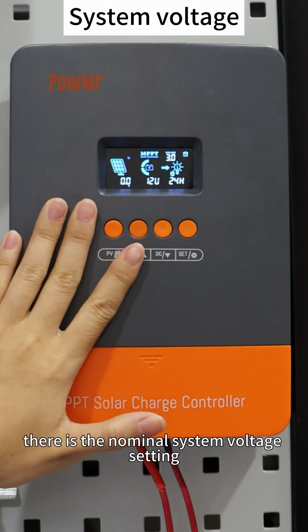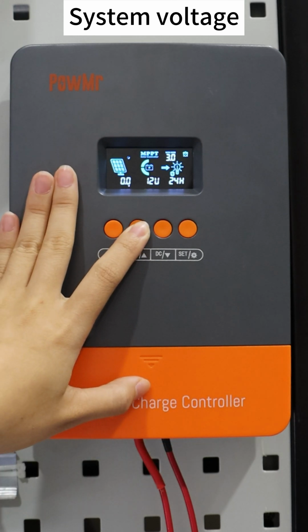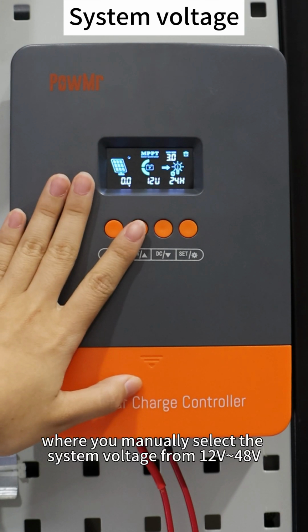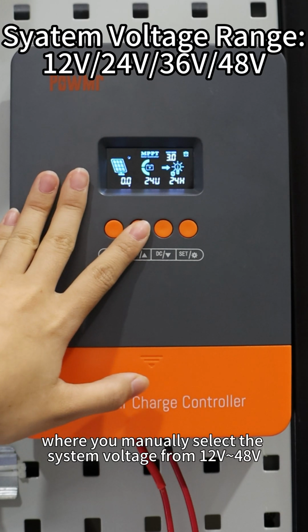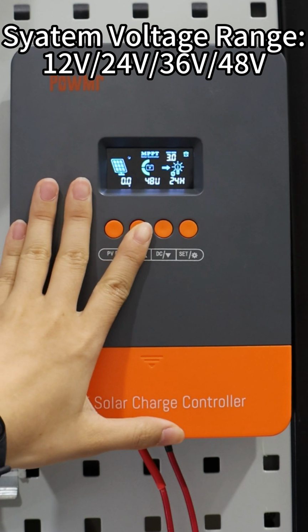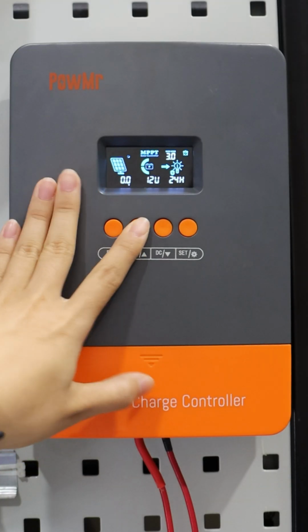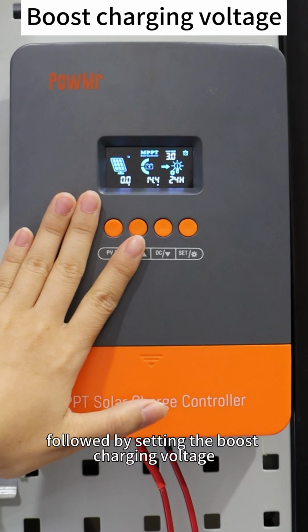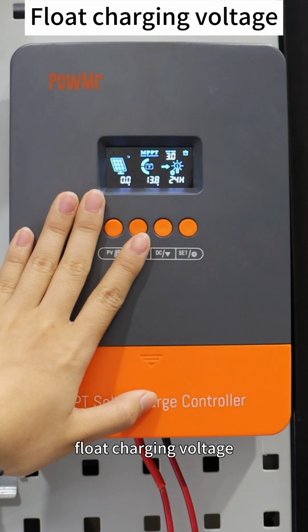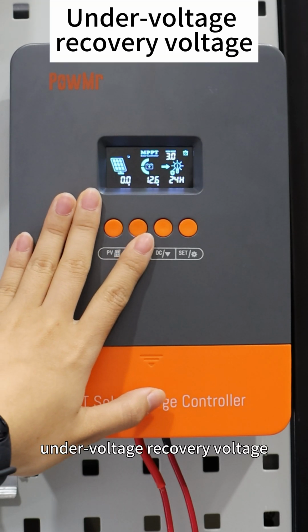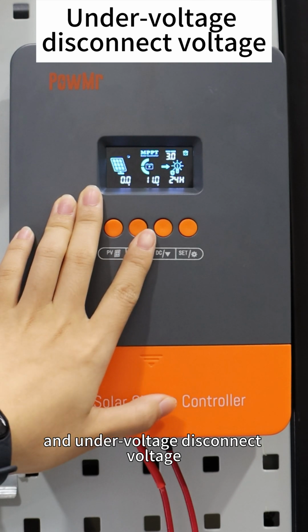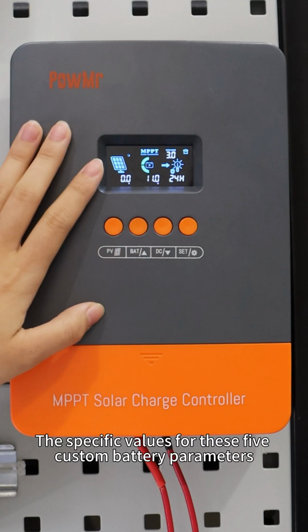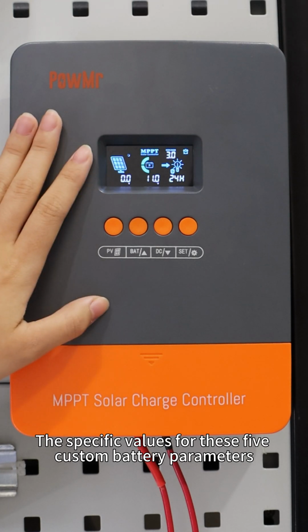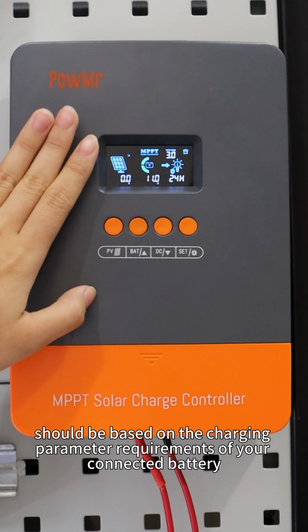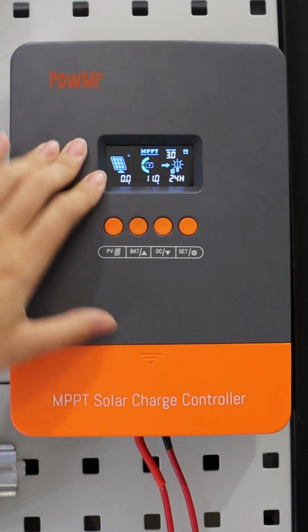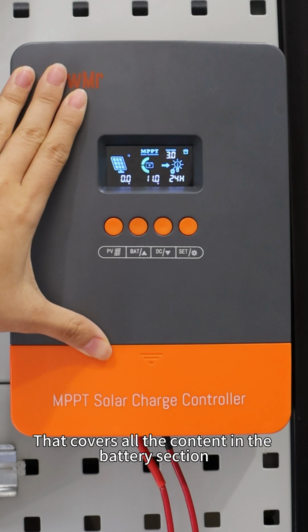Then there is a nominal system voltage setting, where you manually select the system voltage from 12 to 48 volts, followed by setting the boost charging voltage, float charging voltage, under voltage recovery voltage, and under voltage disconnect voltage. The specific values for these five custom battery parameters should be based on the charging parameter requirements of your connected battery. That covers all the content in the battery section.